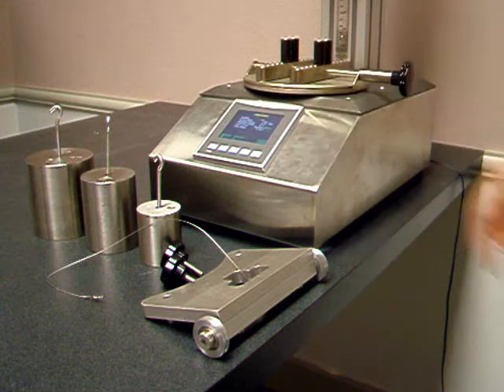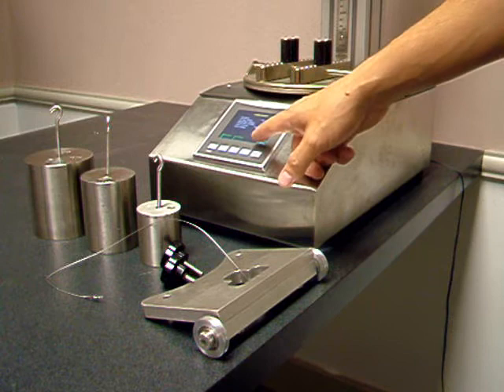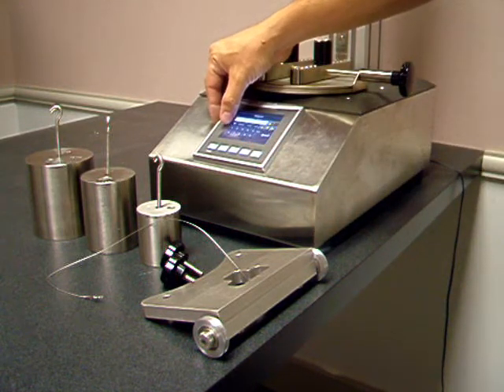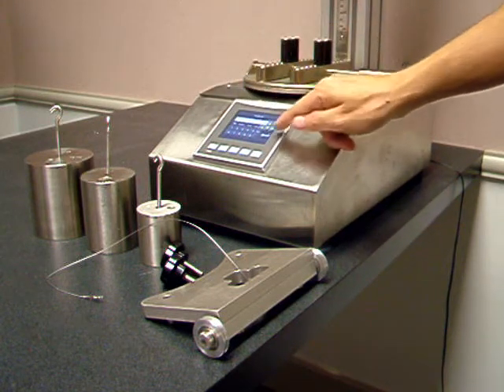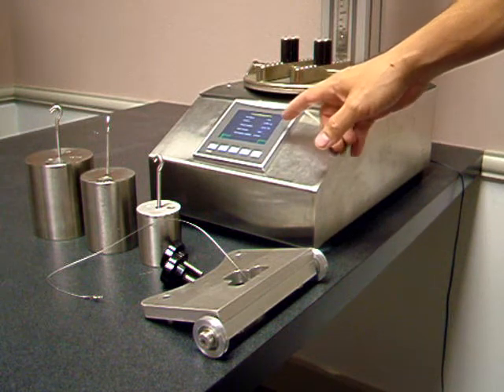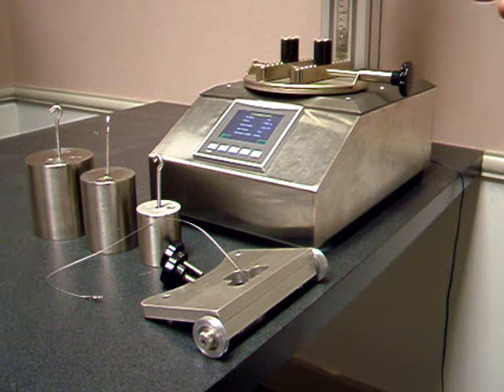You select calibration, and in the calibration you press the recal button. The default password to enter the calibration mode is 1113, and then you hit enter. On the next screen you will see the weight, the pulley radius, and the unit system to be used in the calibration.